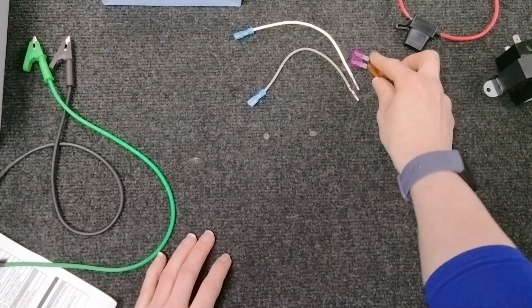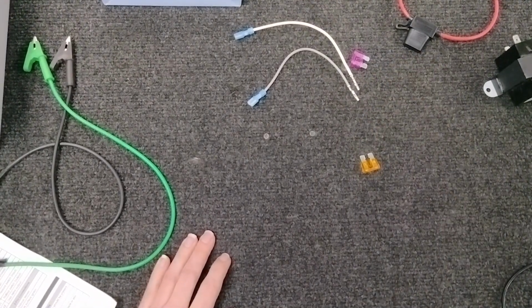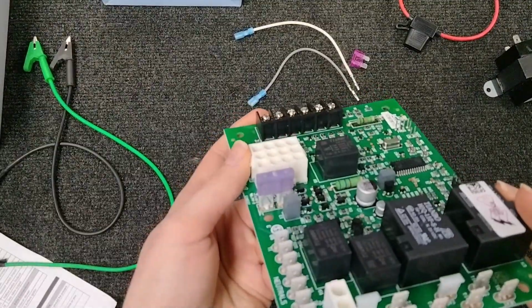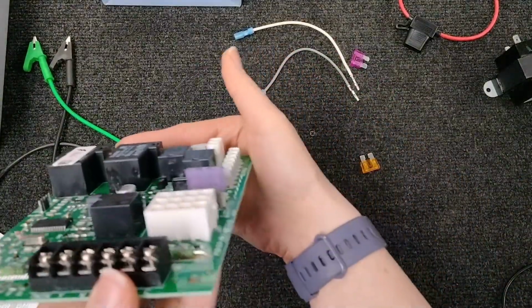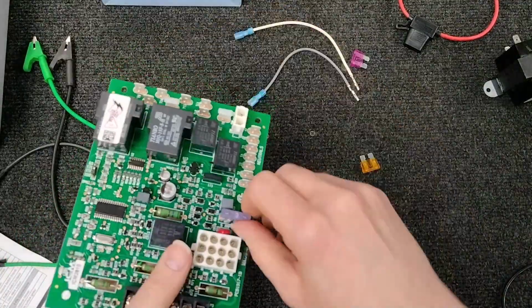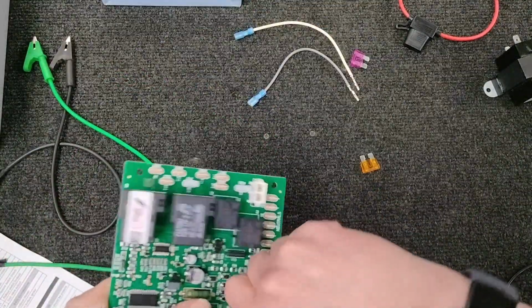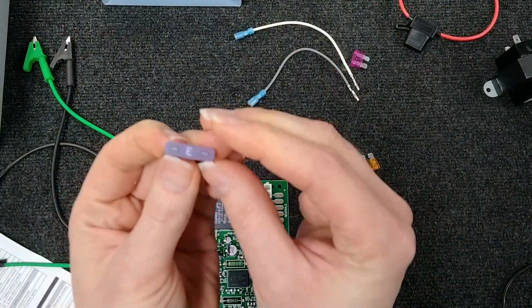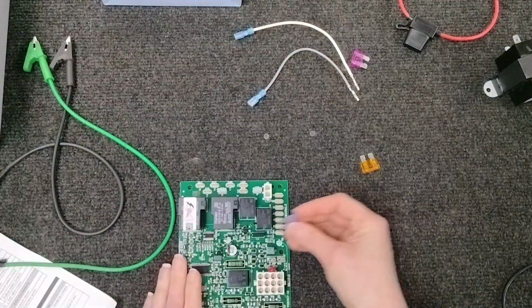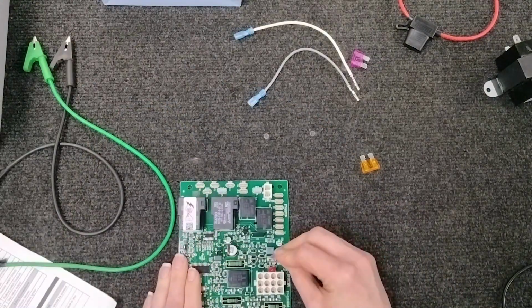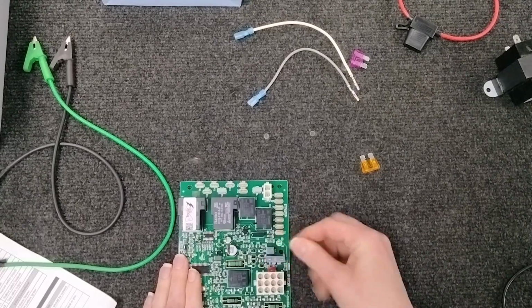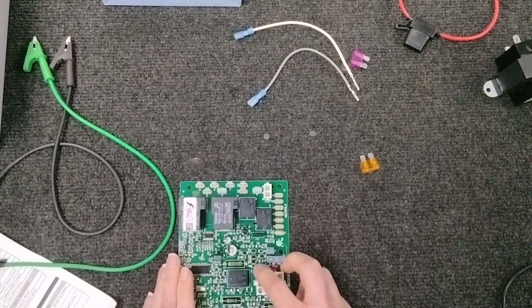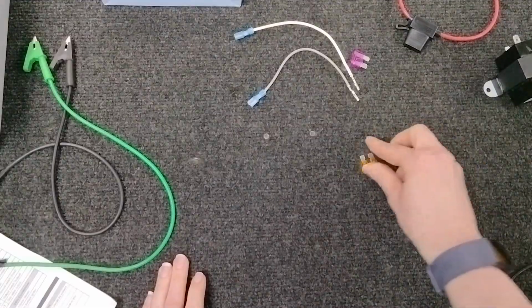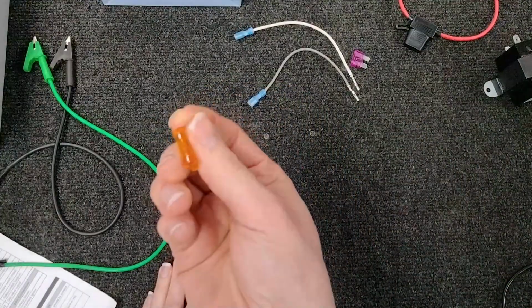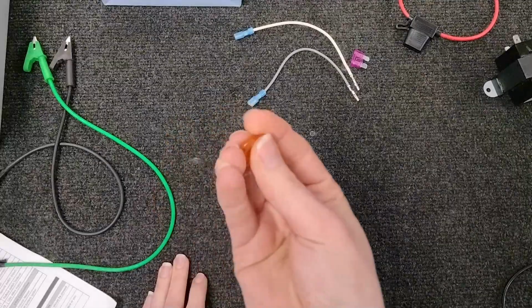One of the things it's also good to check for is on your control board. Now, some of the older units might not have these, but you should have somewhere on your board this guy, which this is a 3-amp fuse. Some of the Trane and a few other models I've seen, I'm pretty sure some of Amana did some 5-amp for a little bit as well. You'll see 5-amp fuses like this.